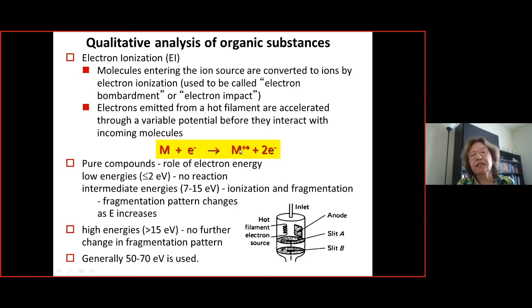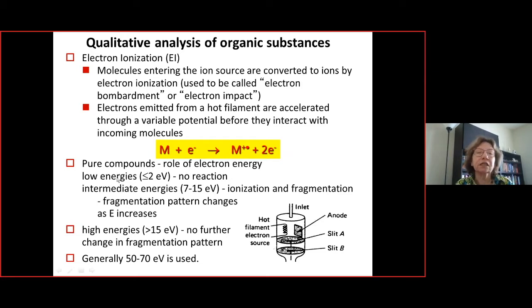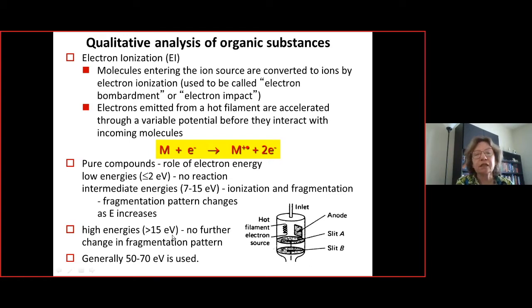This process is described by: M + e⁻ → M⁺• + 2e⁻. The analyte loses an electron, becoming a cation radical, denoted M⁺•. We can vary the electron energy; at 7–15 eV, ions begin to appear and fragment. Above a certain threshold, the fragmentation pattern stabilizes, providing a molecular fingerprint. Typically 50–70 eV was used for electron ionization.